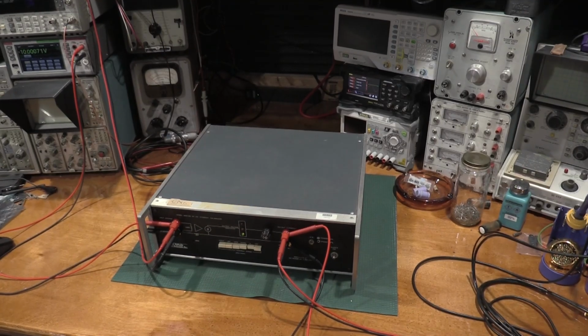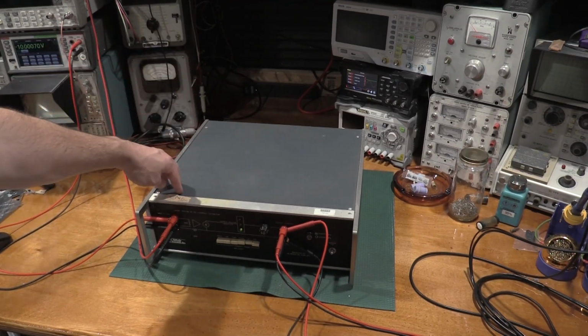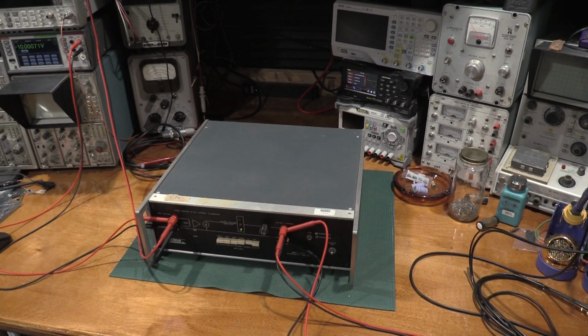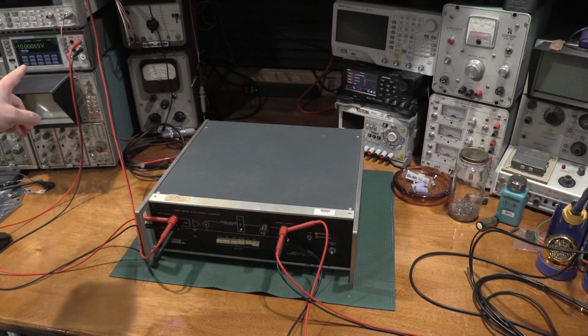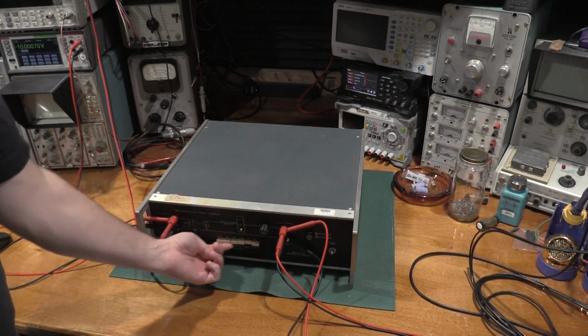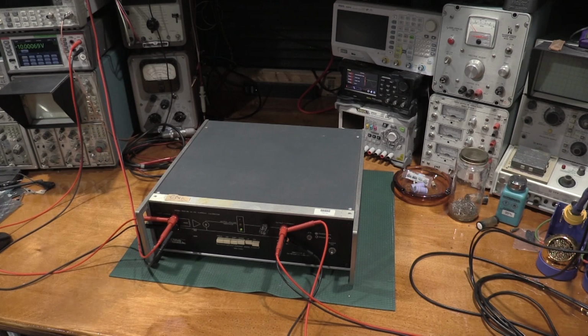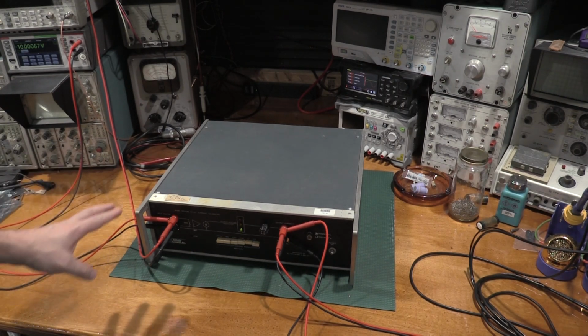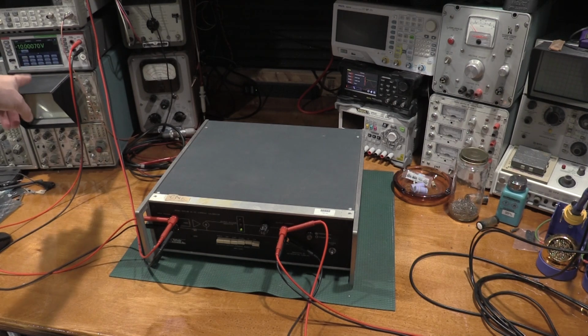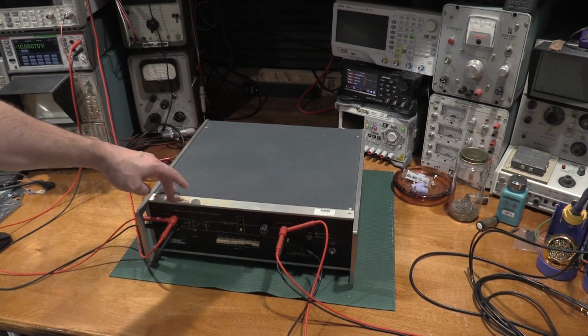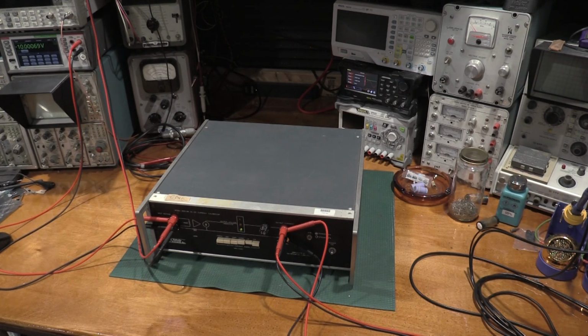Okay, we have a couple more connections to the 2500. I was having some trouble with the 6500 reading the compliance voltage, or not the compliance voltage, the current. It was reading out of spec. That could be a couple of things. This could need to be calibrated. This could also need these switch packs cleaned. But I changed some things. I'm now monitoring the voltage on the input to make sure it was stable to 10 volts, which it is. We're not bouncing very much. Actually, I think I may bring it down to see 10 volts even.